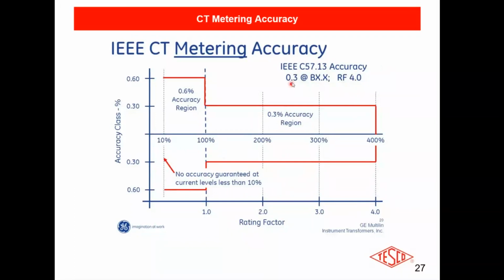So 0.3, you would think that if it's a 400 to 5, and you were to put, say, 200 amps through it, you should get 0.3% accuracy, and you'd be wrong. Because it's a 400 to 5, that thermal rating factor of 4.0 means you could go up to 1,600 amps through it, and as long as you don't exceed your burden, you should get 0.3% accuracy.